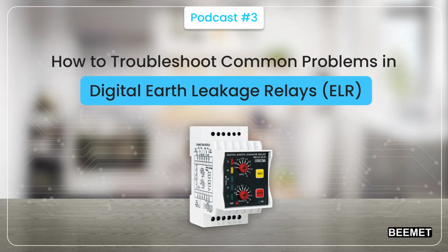No trip at actual leakage. Here, a real ground fault exists, but the ELR does not respond. This can lead to insulation breakdown, equipment damage, or shocks. What to check? Use a relay testing tool such as ELR injection tester to simulate rated leakage and observe response time. Check the CBCT output voltage for saturation or damage.